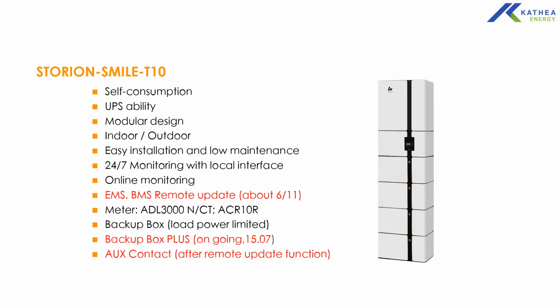It's a 3-phase. It would need a meter. It's a hybrid inverter. So if it's connected to grid, definitely you need a meter, a 3-phase meter, and the comms cable will be wired to the inverter. So the meter comes either as a pass-through meter, that is all power passes through the meter directly, or as a CT meter. You can actually wire the meter to measure your load consumption by putting CTs to the system, especially if your premises are quite big, because the pass-through current is 80 amp. So if your breaker is way more than 80 amp, then definitely you would need to use CTs.